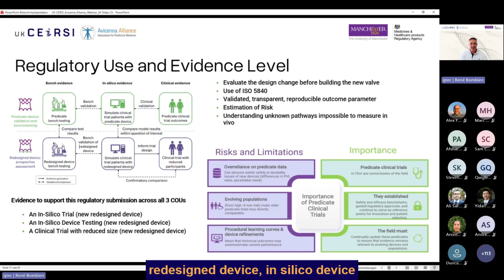For regulatory use and the evidence level, what we could add with this model, we could add an in-silico trial with the redesigned device, in-silico device testing with the redesigned device, and a clinical trial with a reduced sample size. What we get out of this, we could evaluate the design change before actually building a new valve, also using, of course, the standard, that is the 5840 standard. We would have validated, transparent, and reproducible outcome parameter, and an estimation of risk. And in the end, of course, an understanding of these unknown pathways that you impossibly can't measure in vivo.